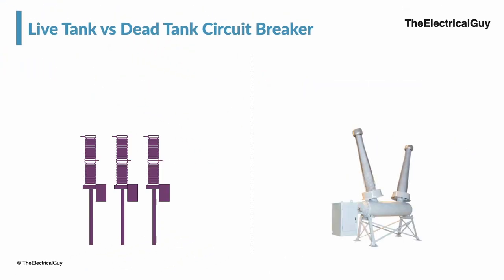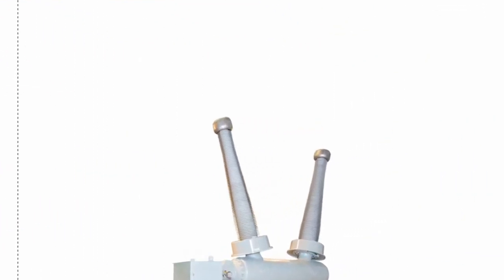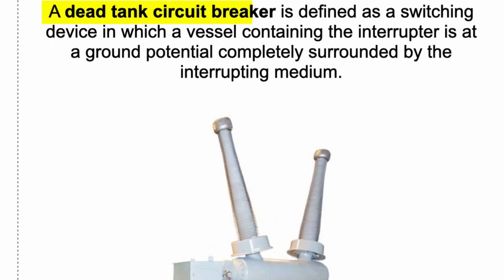A live tank circuit breaker is defined as a switching device in which the vessel containing the interrupter is at a potential above ground. On the other hand, a dead tank circuit breaker is defined as a switching device in which the vessel containing the interrupter is at ground potential, completely surrounded by the interrupting medium.